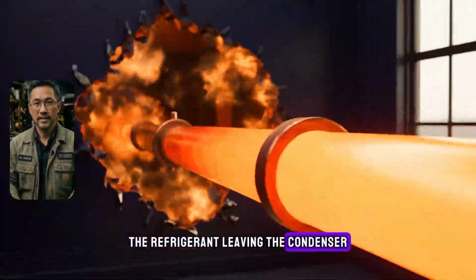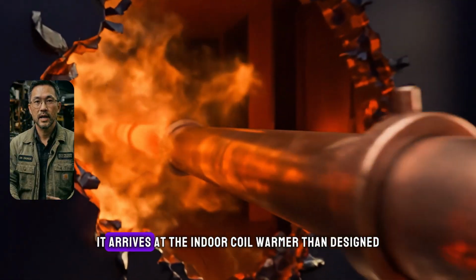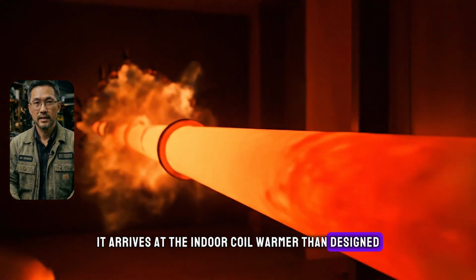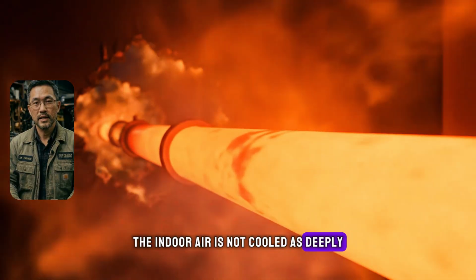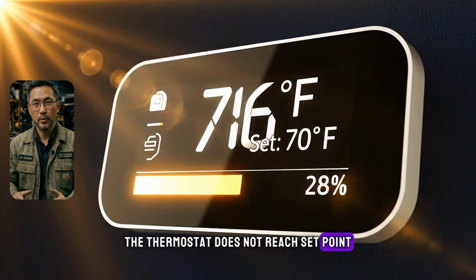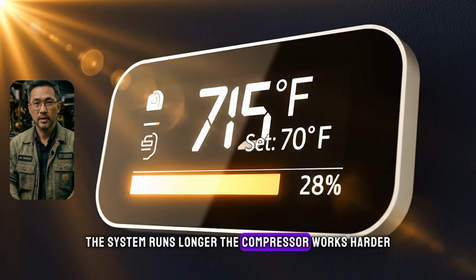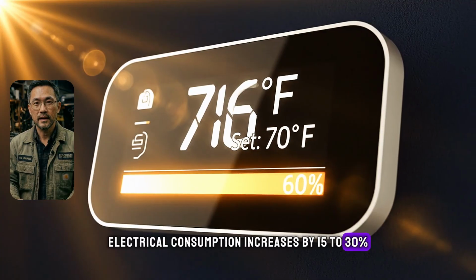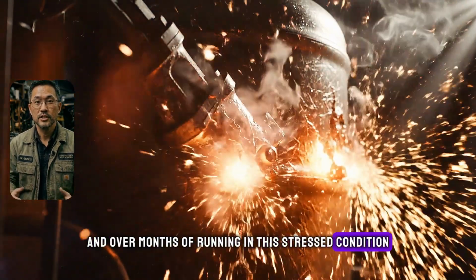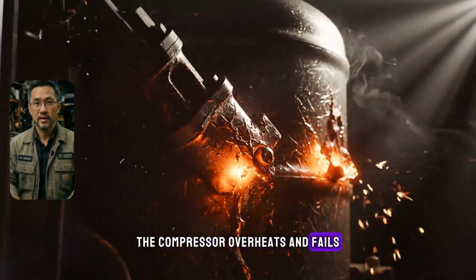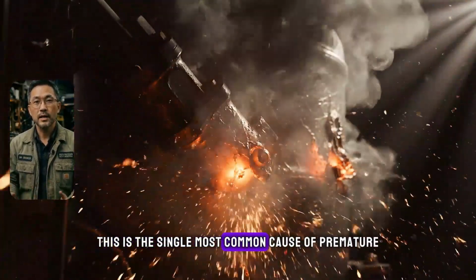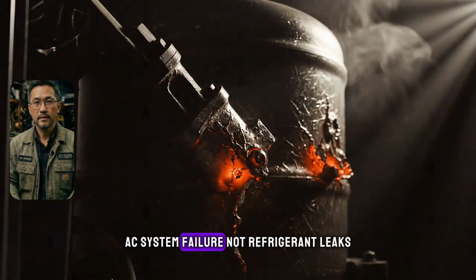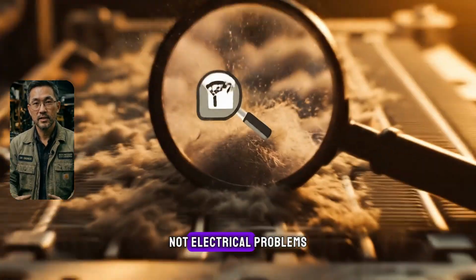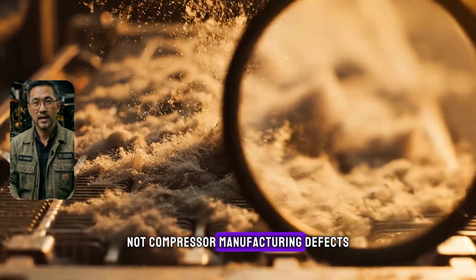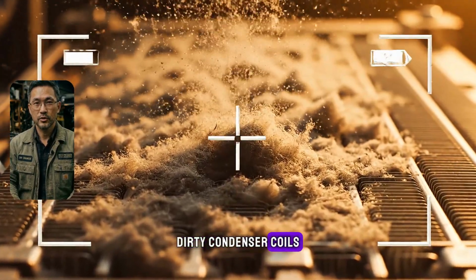The refrigerant leaving the condenser is not cooled sufficiently. It arrives at the indoor coil warmer than designed. The indoor air is not cooled as deeply. The thermostat does not reach set point. The system runs longer. The compressor works harder. Electrical consumption increases by 15 to 30%. And over months of running in this stressed condition, the compressor overheats and fails. This is the single most common cause of premature AC system failure. Not refrigerant leaks, not electrical problems, not compressor manufacturing defects, dirty condenser coils.